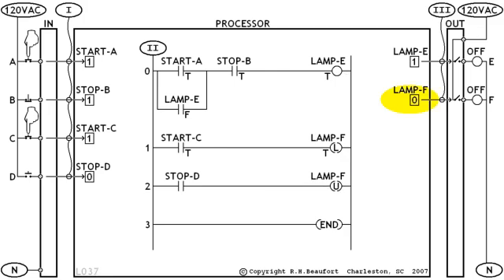So based on the true logic coming into the latch, the processor goes to the bit and writes a one into the box. Many people believe that a one written by a latch is somehow different from a one written by an OTE. That's not correct. The most common misconception is that once a bit has been turned on by a latch, then it can only be turned off by an unlatch. That's wrong too. Actually, anything capable of writing a zero into the box can easily turn off a latched bit. Now let's move on.